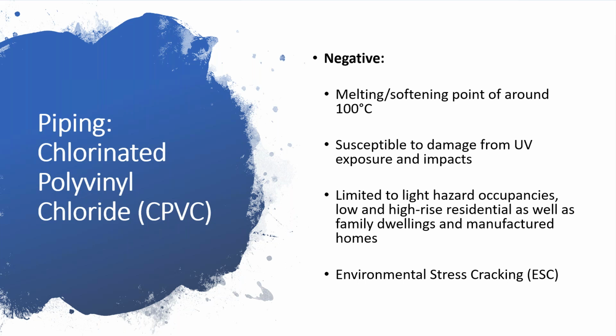What are the negatives? Well, obviously, the melting or softening point is around 100 Celsius. Again, don't be too concerned about this. The CPVC, even though it starts to soften, still functions while exposed to heat. It just starts to char, and it will last less time in a very intense heat as compared to steel, but it will perform. It is susceptible to damage from UV exposure. So if you leave it outside in the sun, it's going to degrade and produce some damage to it. Obviously, if you step on it or impact it, it's going to crack, and that's never good.